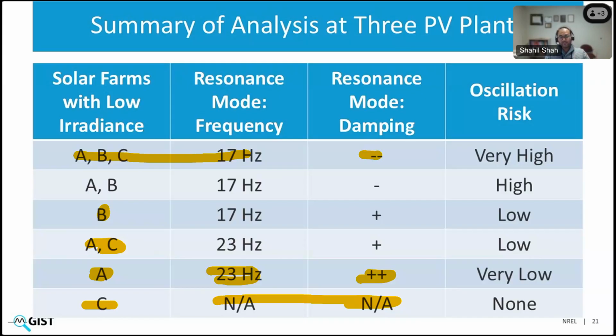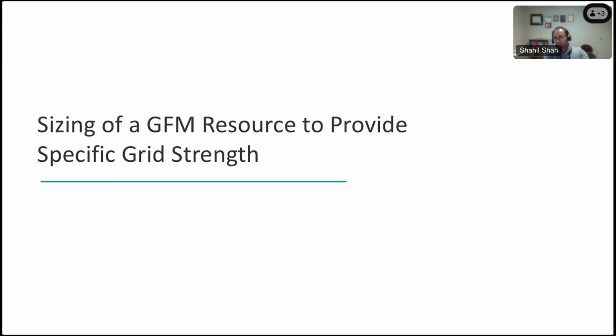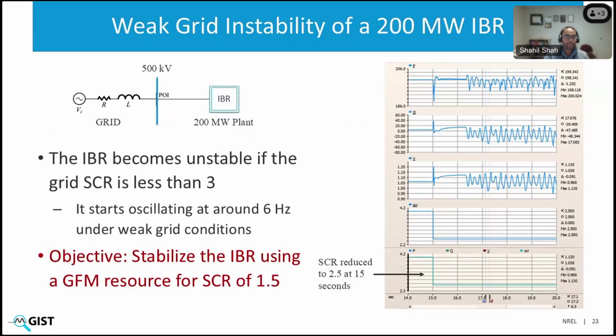So now you can rank the IBRs which are contributing to these oscillations and decide where you will do the control upgrades, which plant you will prioritize to either make changes to the system or make changes to the controls to mitigate these oscillations. So what I talked about was all about detailed analysis of understanding where the oscillations are coming from, but how do we mitigate them in the planning stages, and how do we size grid forming resources to provide specific grid strength? That is what I'll talk about in the next few slides before moving on to Q&A.